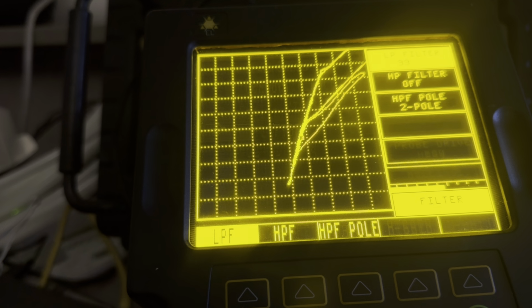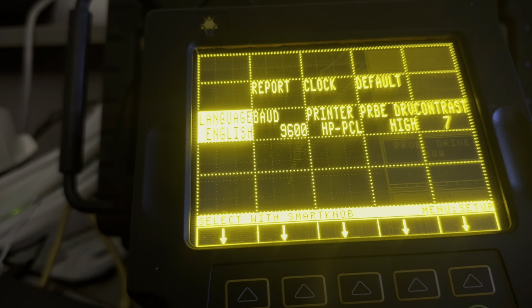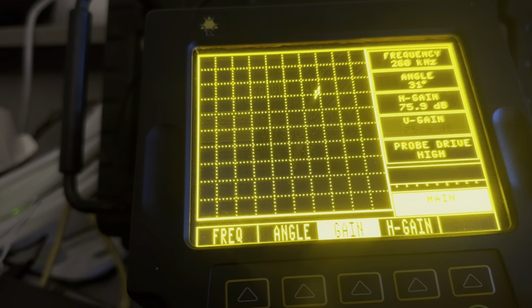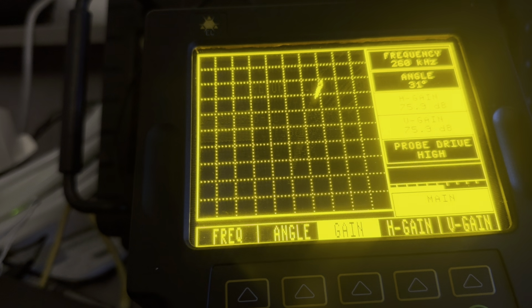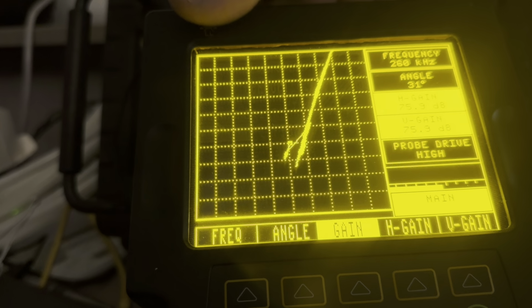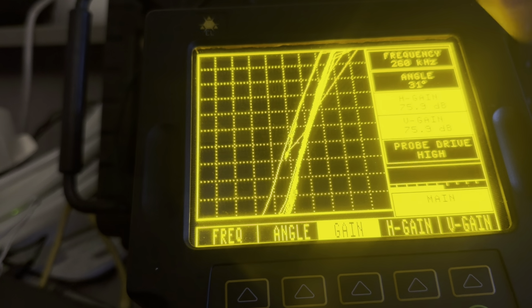So we adjusted the drive voltage to high. So obviously that's what this particular coil likes. And then on the adapter, we switch it to the reflection mode because this is a driver pickup probe, which means it has a driver coil and a much smaller pickup coil inside of it. And then we had the choice of high, medium, and low on our selector. That's, I think, the high setting.